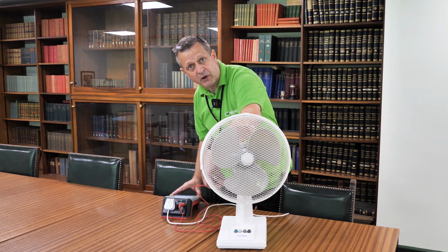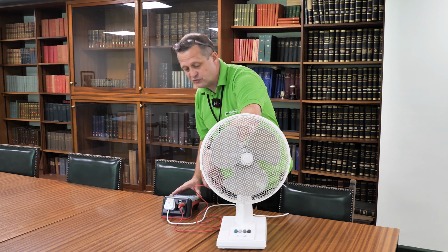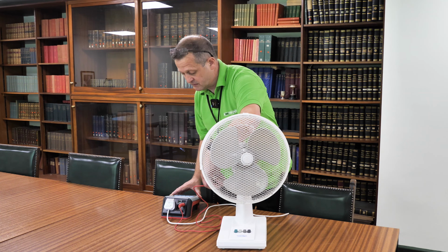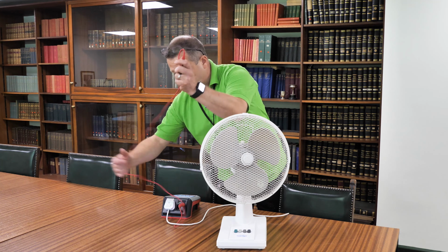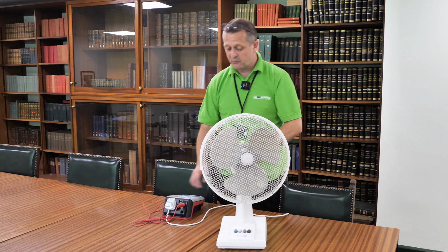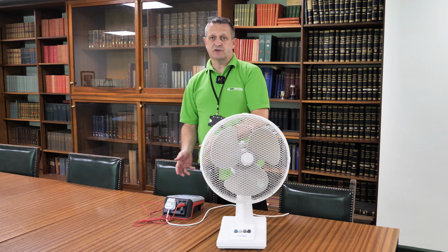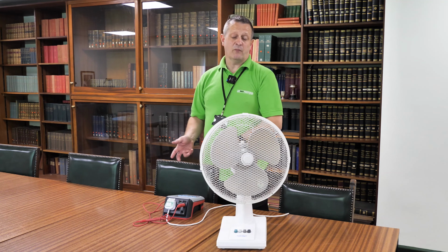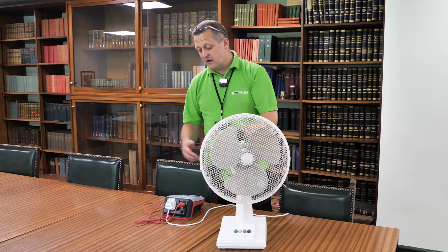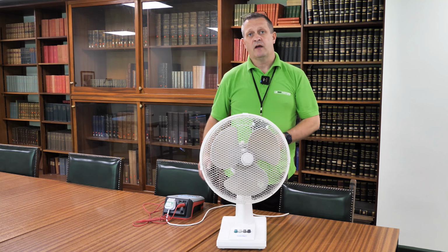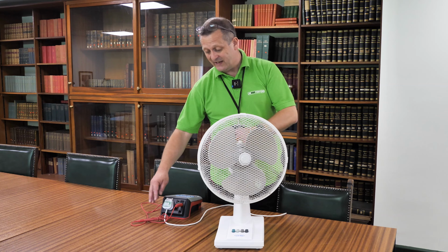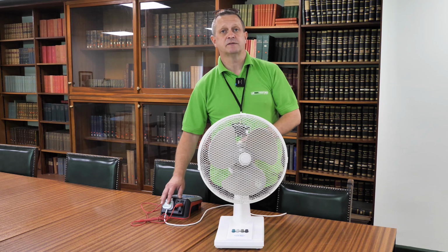So we're going to do that to complete the circuit. Select a class 2 appliance test, and it'll go through the insulation resistance test. That's showing perfectly fine. That's quite simply the class 2 test complete. We then annotate all the details onto the device, or whichever method you use, and the test is complete once we've applied a label on a clean, clear, visible place on the appliance.